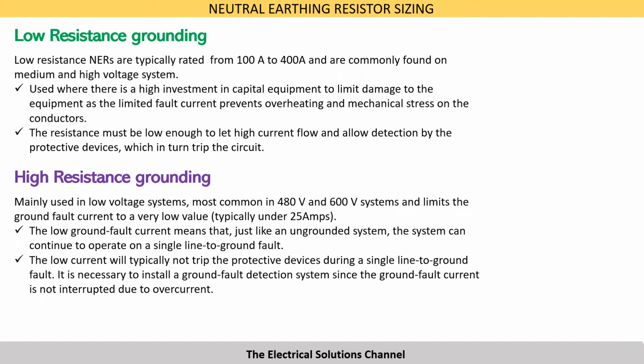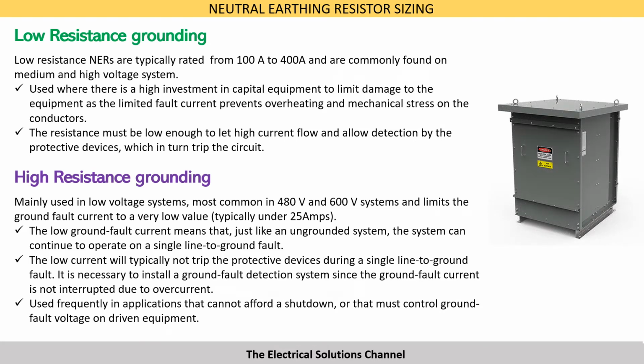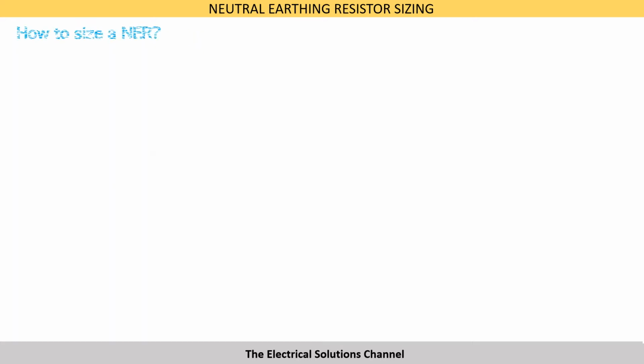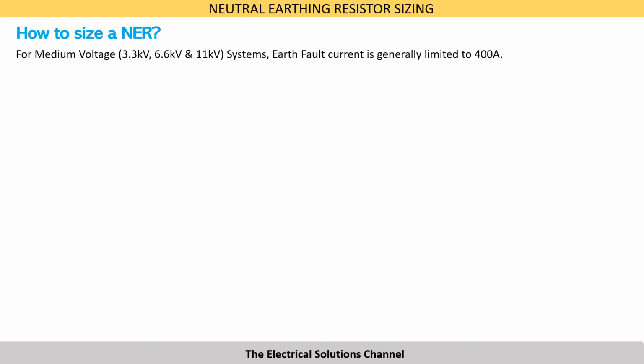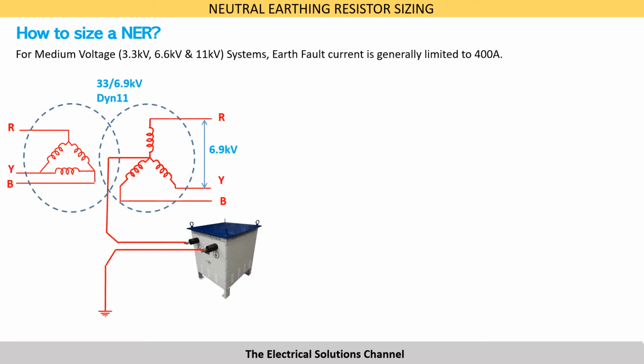It is necessary to install a ground fault detection system since the ground fault current is not interrupted due to overcurrent. These are frequently used in applications that cannot afford a shutdown or that must control ground fault voltage on the driven equipment. Let us now try to understand how to size a NER. For medium voltage systems, typically for 3.3 kV, 6.6 kV and 11 kV systems, the earth fault current is generally limited to 400 amps.